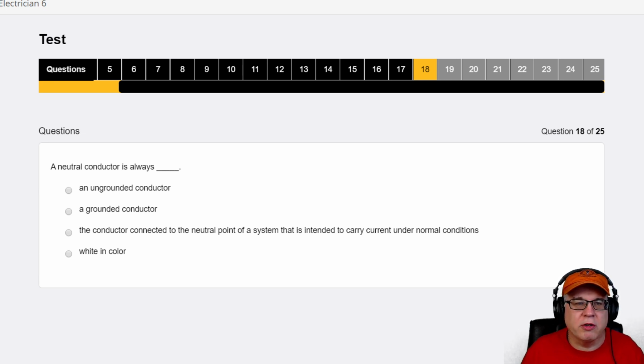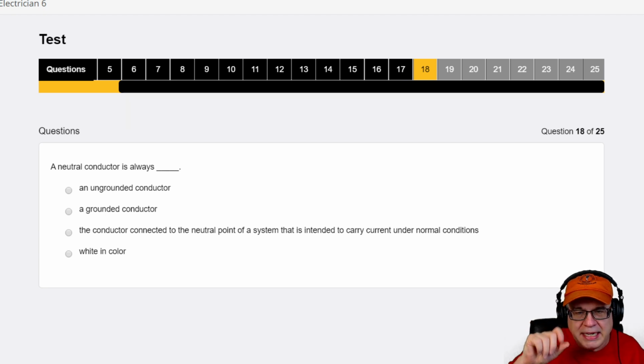All right, so neutral conductor. Now, a neutral conductor is, just a little lesson here, always a grounded conductor. But a grounded conductor is not always a neutral. Boy, that sounds cryptic, doesn't it? So again, a grounded conductor is intentionally connected to Earth, intentional, right? A neutral conductor is a certain point on the transformer, whether it's a mid-winding or if it's a Y transformer, it's a midpoint. If it's a delta, it's halfway between the phases, a midpoint on a winding.